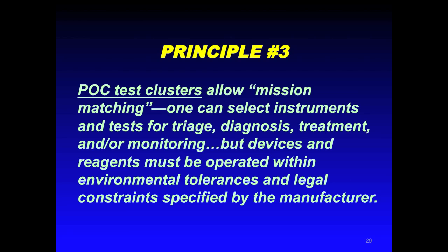Let's launch forward then with Principle 3, assuming now that we have established our needs. We're going to next select point-of-care test clusters. These test clusters should allow mission matching. That is, one can select instruments and tests for triage, diagnosis, treatment, and/or monitoring, but devices and reagents must be operated within environmental tolerances and legal constraints specified by the manufacturer.